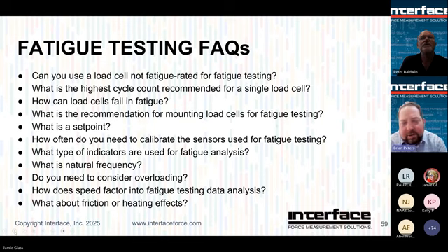Now, some things could go wrong with a bridge. It's rare. If you are doing fatigue testing, we didn't mention this thus far, but we typically would recommend dual bridge. It's very common. Some of our customers even do triple bridge for their fatigue test setups. So why a second bridge?